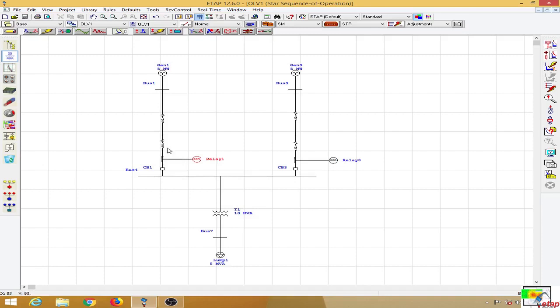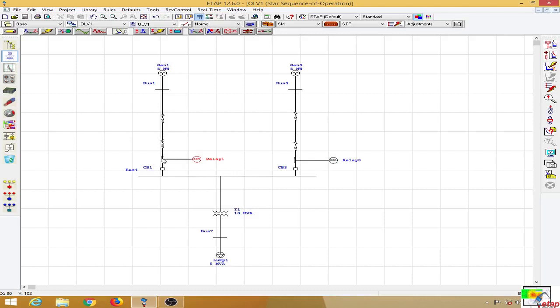When I mention direction, I am referring to the CT dot convention. When the current flows into the dotted terminal, we say the direction is forward. When the current flows into the non-dotted portion, we say it is in the reverse direction. Protection engineers follow the convention that the non-dotted portion should be towards the device to be protected, and the dotted portion — referred to as the P1 terminal — faces away.